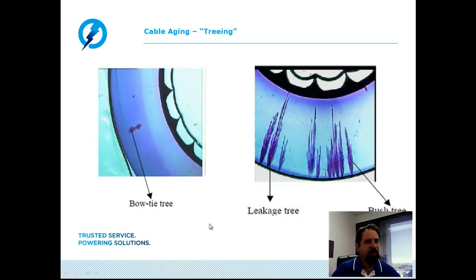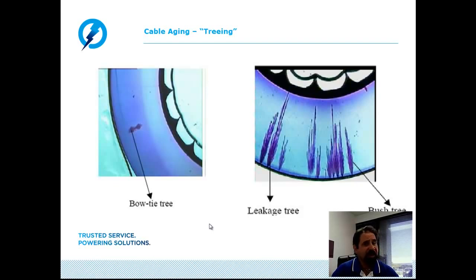Bowtie trees are water trees that grow from within the insulation outward toward the surfaces, growing in the direction of the electric field in both directions toward the two electrodes — the center conductor and the concentric neutral surrounding the cable. Bowtie trees have a faster initial growth rate compared to the vented tree; however, they are not capable of growing to large sizes and usually do not grow to a size significant enough to cause a failure in the insulating system.